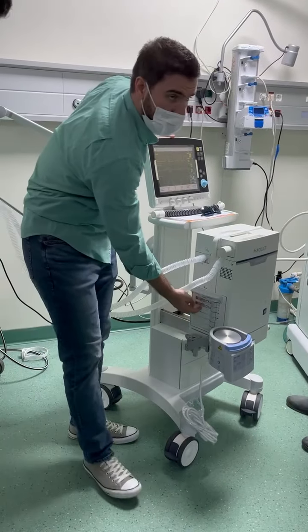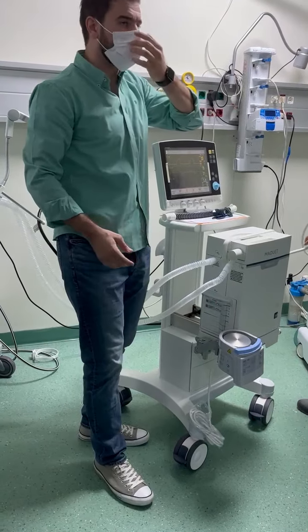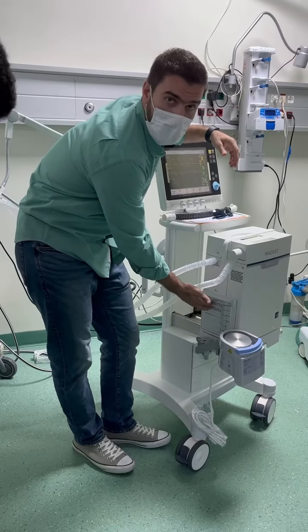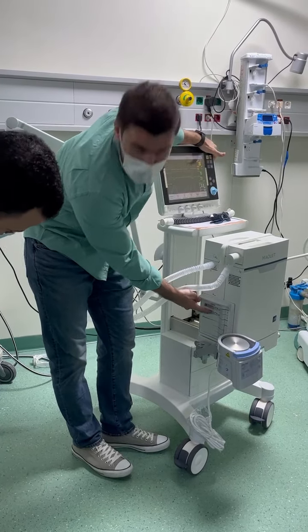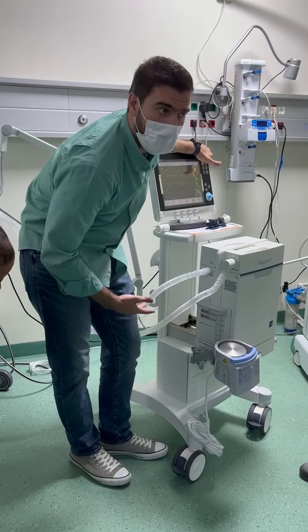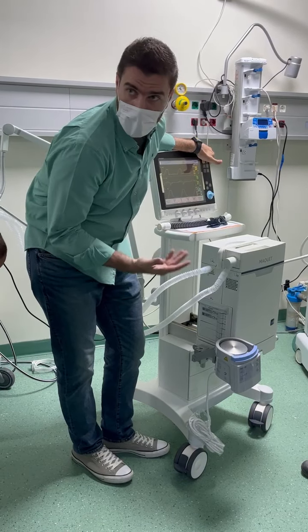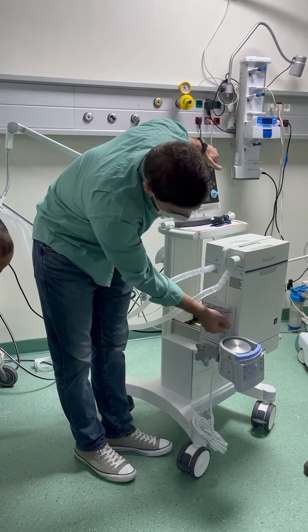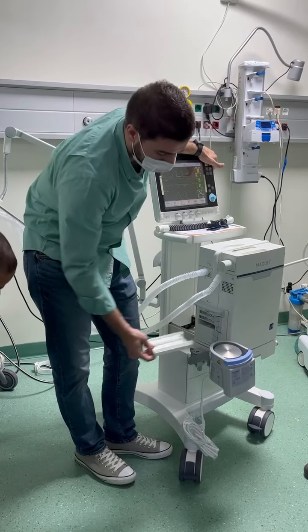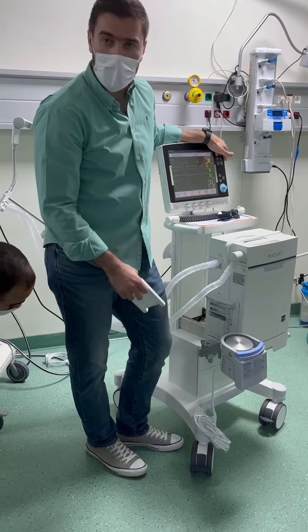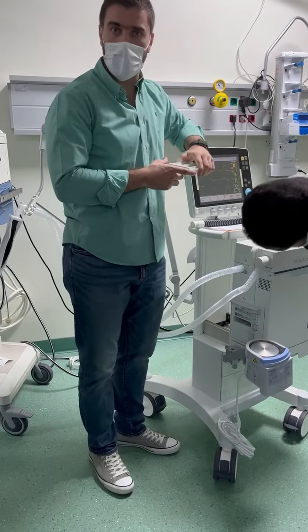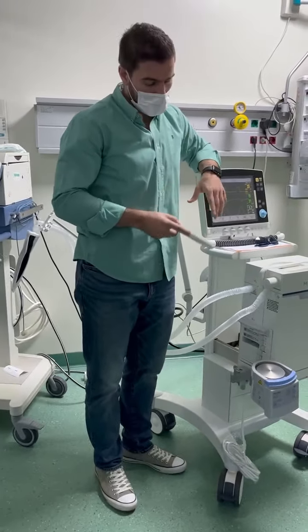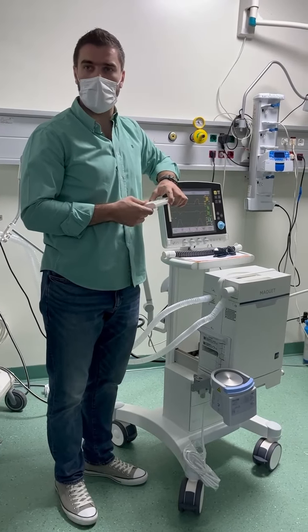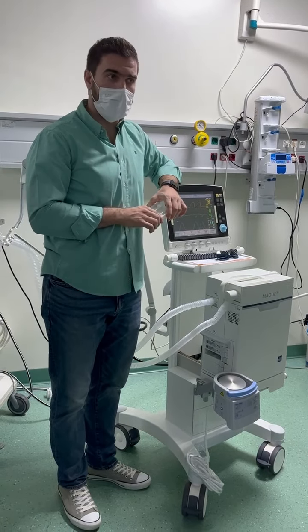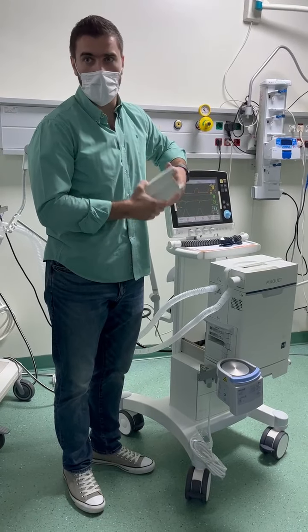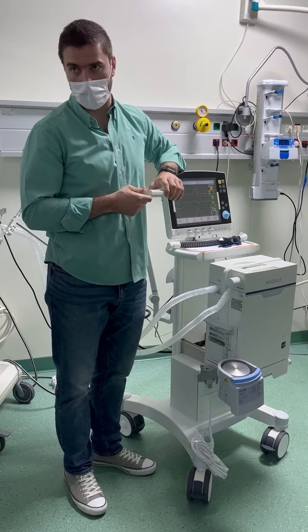This is called module parts. What do we need in this module? First of all, the machine comes with two batteries. You can see there are 2 batteries here. In the future, if you need to expand the ventilator for more batteries, you just get the new battery, take this cover, put the new battery in. Okay. Each battery will work around 1 hour, 55 minutes to be exact. So 2 batteries will work around 2 hours. Of course, it depends on the mode you are working on. Different modes, different battery consumption.